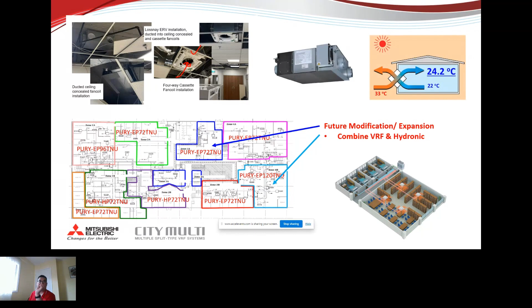And once you reach set point, maybe the valve can be at minimum position, still trying to react to what's required, opening and closing. So it's all being done automatically in the back end. So what I want to say is the fan coil unit will self-regulate depending on the valve position. And the larger the opening, the more refrigerant needs to be processed by the condenser. And the condenser will be able to automatically increase or decrease its speed. And this fan will also increase or decrease, depending on how much heat needs to be discharged, as well as outside wind speed.